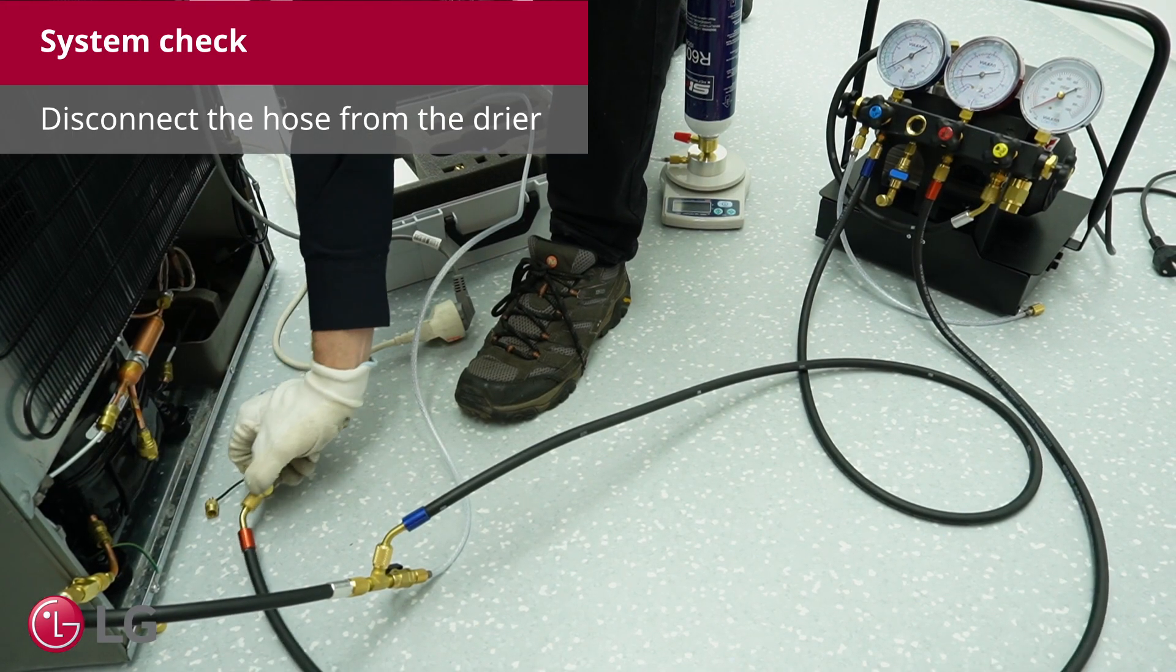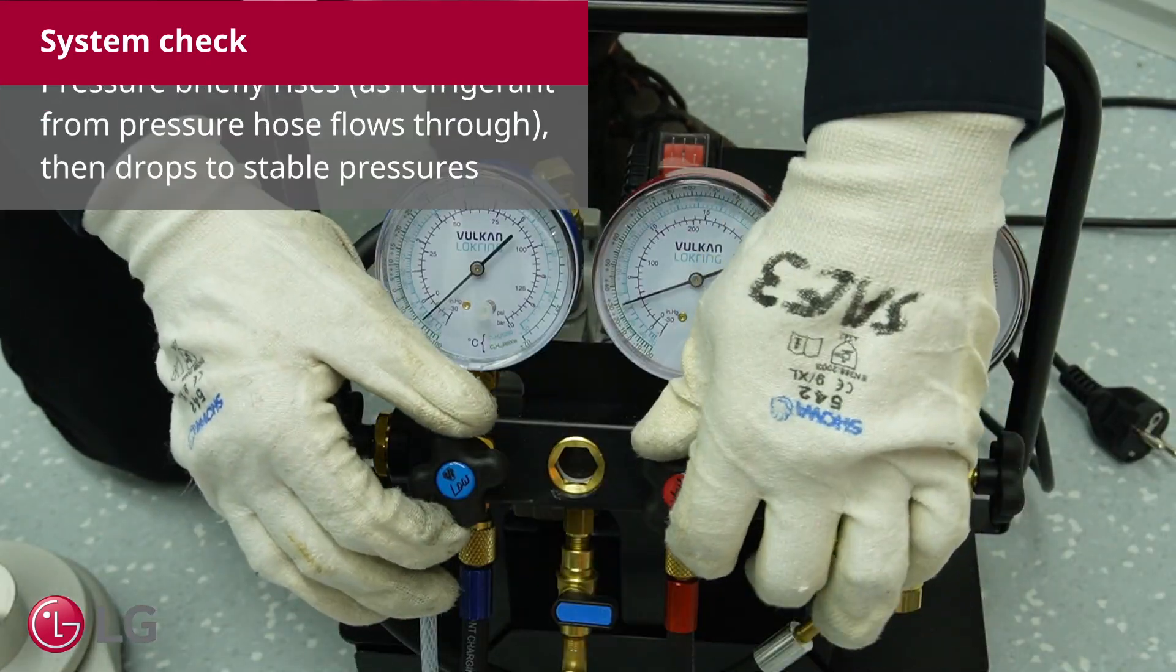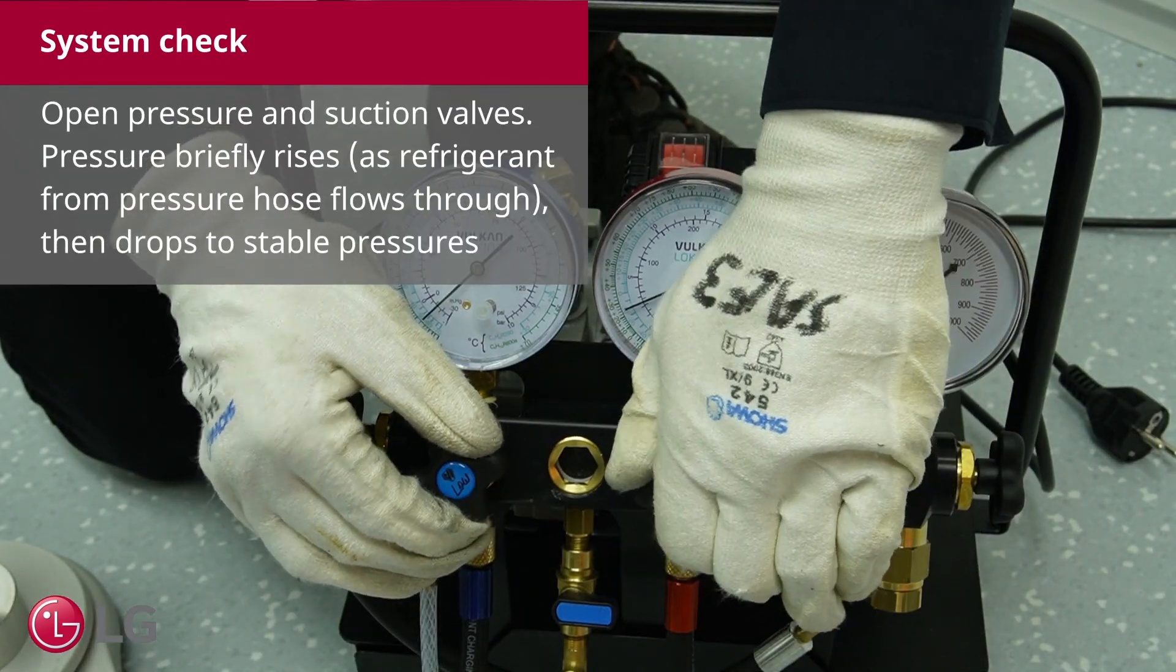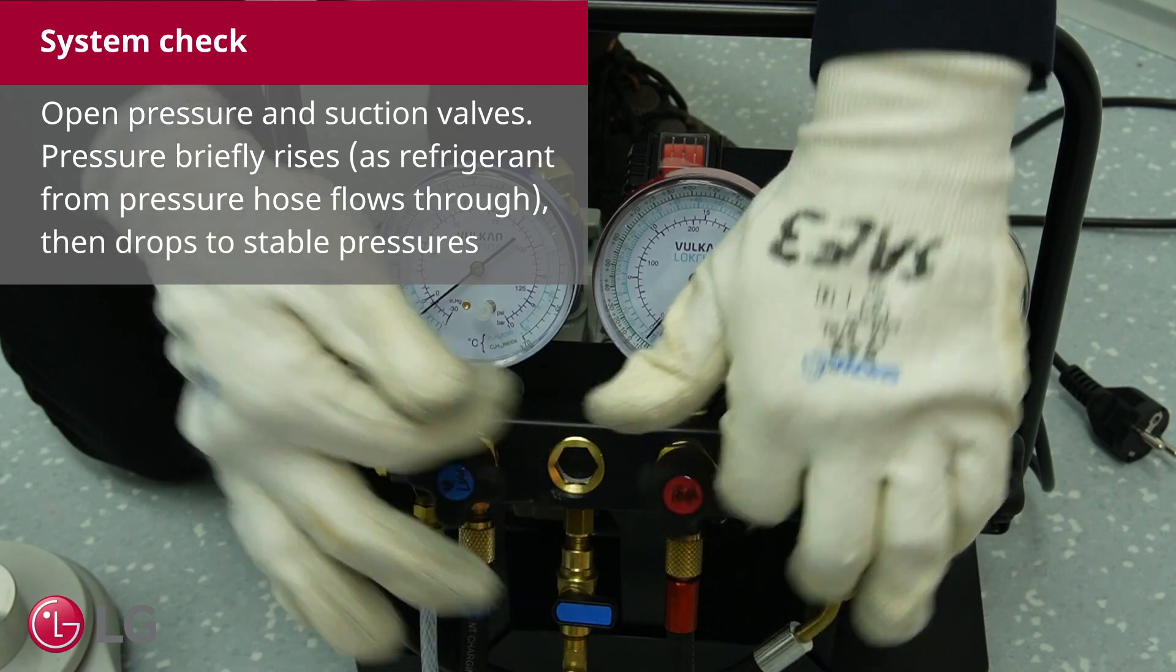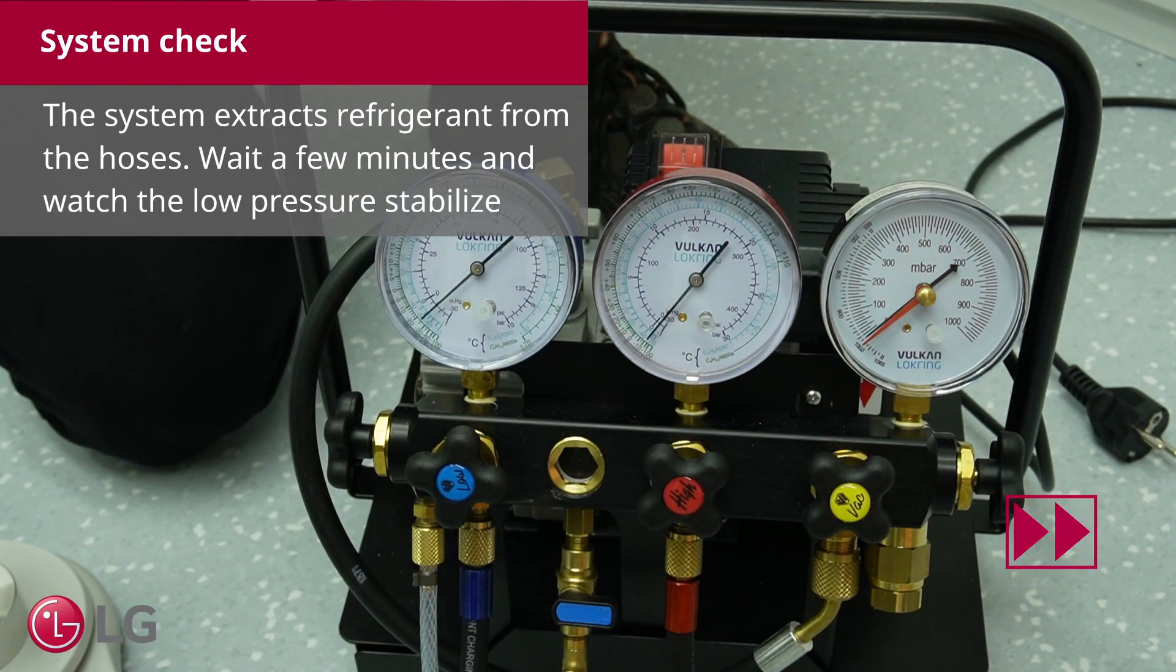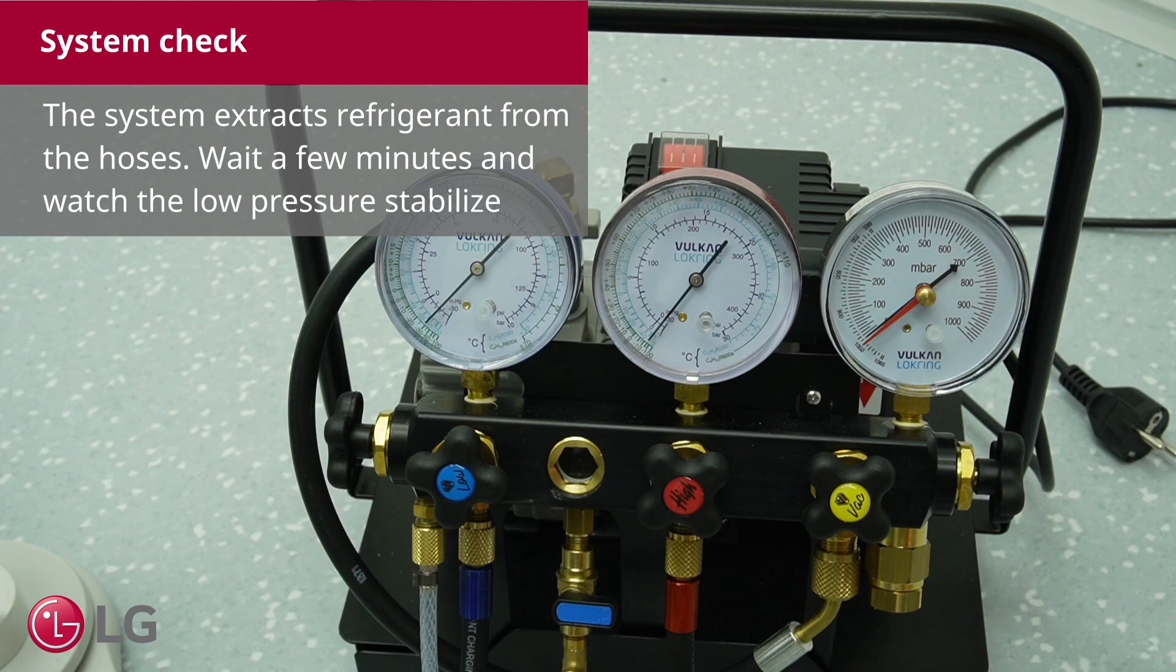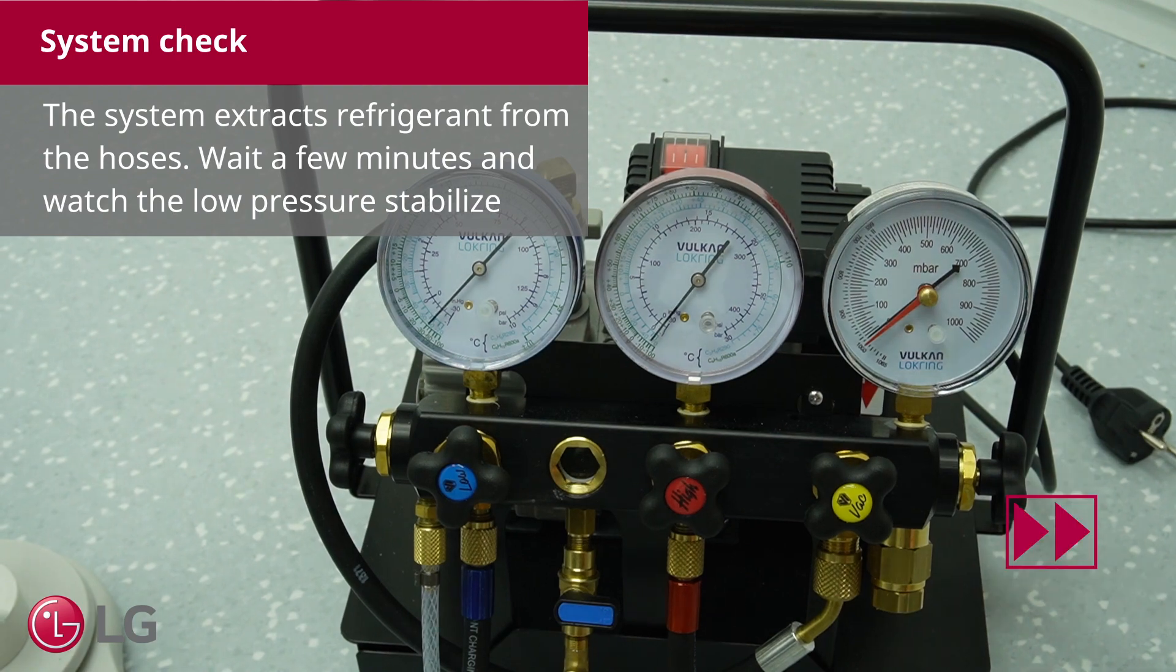Disconnect the hose from the dryer. Open the pressure and suction valves. The pressure briefly rises and then drops to stable values. The system extracts refrigerant from the hoses. Wait a few minutes and watch the low pressure stabilize.